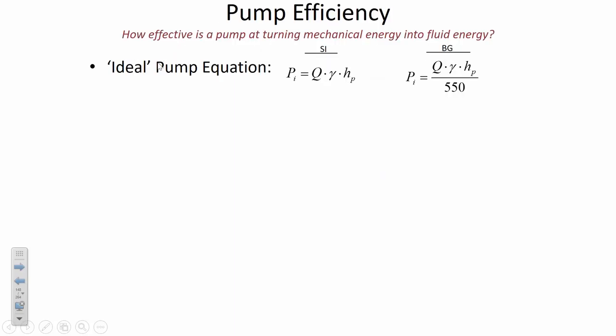Here's the ideal pump equation in both SI and BG units. In SI: flow rate Q in cubic meters per second, times unit weight γ in newtons per cubic meter, times pump head h_p in meters, gives power in watts. In BG units: Q in cubic feet per second, unit weight in pounds per cubic foot, pump head in feet, divided by 550 foot-pounds per horsepower, gives power in horsepower.